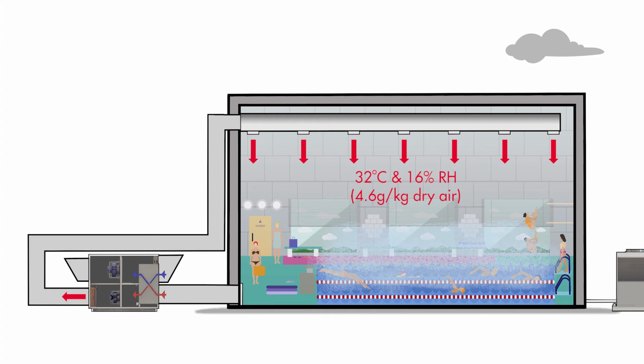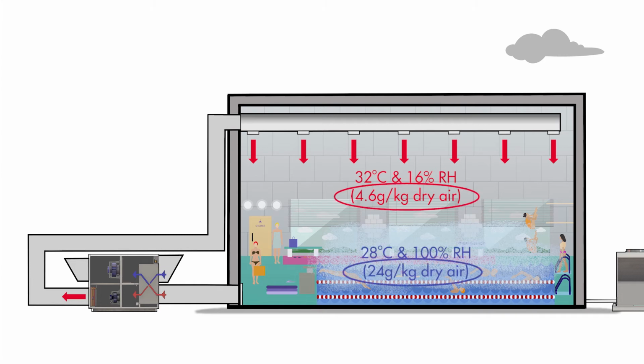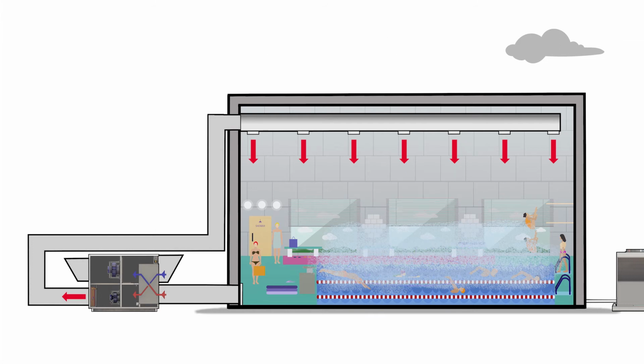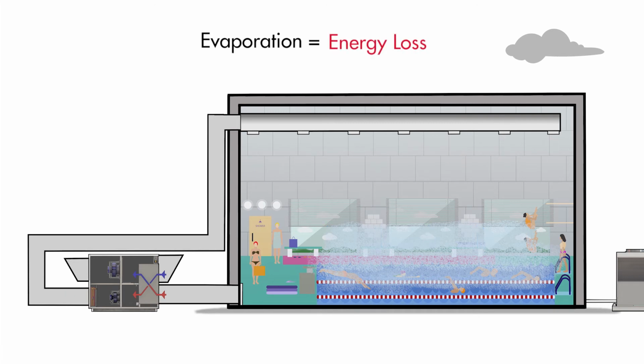increase. This is because the evaporation rate is directly proportional to the difference between the absolute humidity in the air and the absolute humidity of saturated air at the same temperature as the pool water surface. In short, the drier the air and the hotter the water, the higher the evaporation rate. Evaporation from the pool water surface will increase until an equilibrium is reached, where the increased humidity in the air slows the pool evaporation rate to a point where it is equal to the moisture being removed from the air by the ventilation system. And evaporation from a pool equals energy loss. This is because energy that was intended to maintain the pool water at the desired temperature has now instead been used to evaporate water and sent it out through the exhaust system.